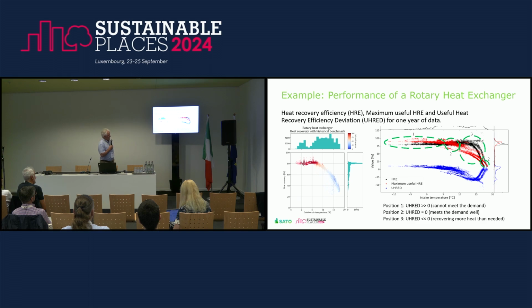On the right side, you can see the evaluation of the performance. The red curve shows the useful heat recovery efficiency—how much heat recovery we actually need to decrease heating consumption, and also decrease cooling energy use. When the outdoor temperature is cold, the black curve shows the actual heat recovery efficiency, and in area number 1 you can see the actual performance is lower than what is useful. This means it would be beneficial to increase heat recovery efficiency. If this difference is big, we could consider whether it would be economically beneficial to change the heat exchanger to a more efficient one. In this case, it's quite close, so probably it's not economically beneficial to replace the heat recovery wheel.